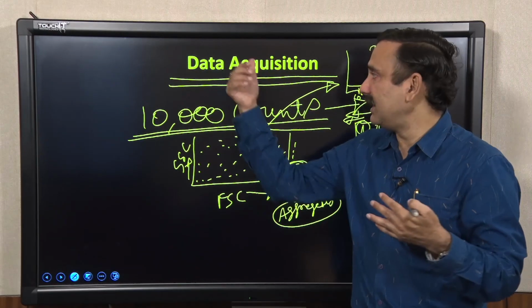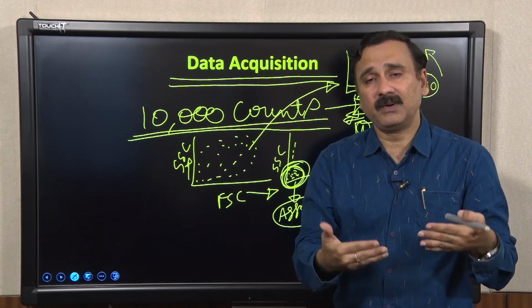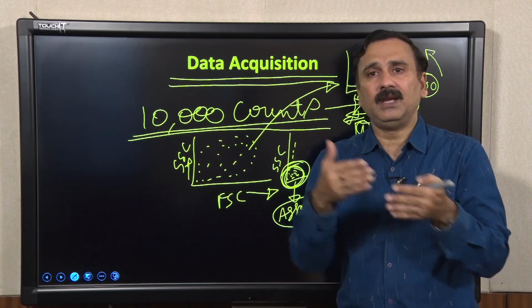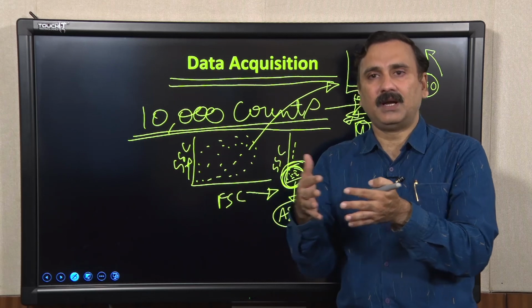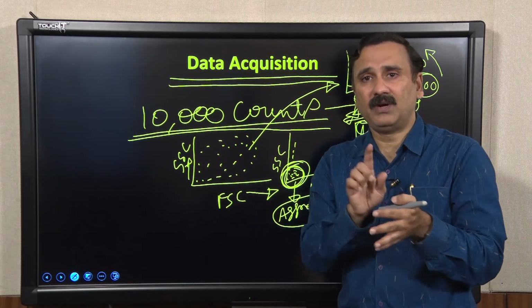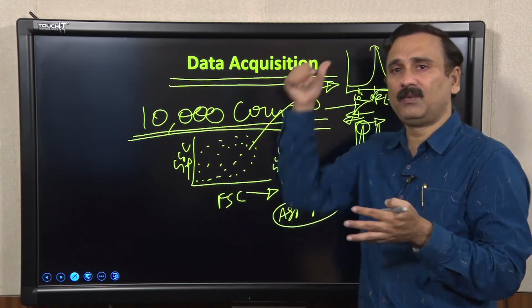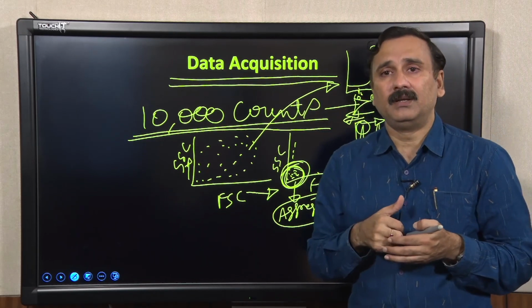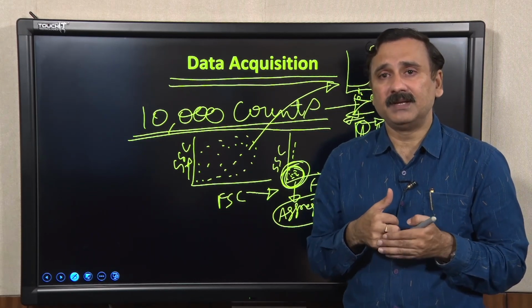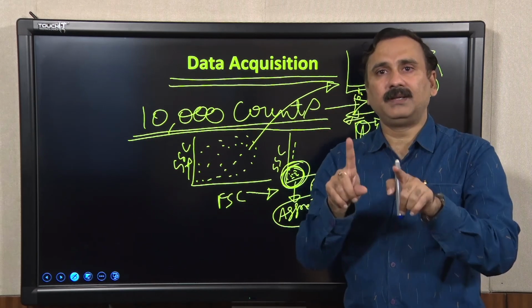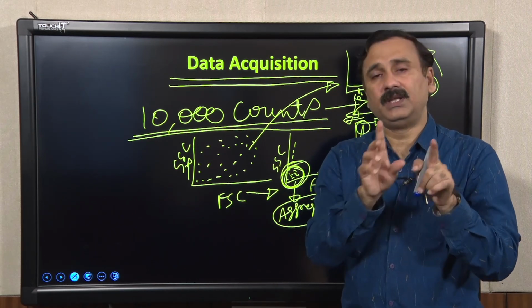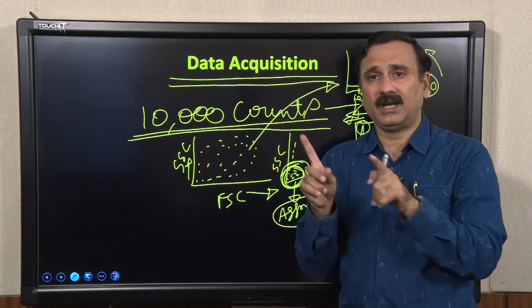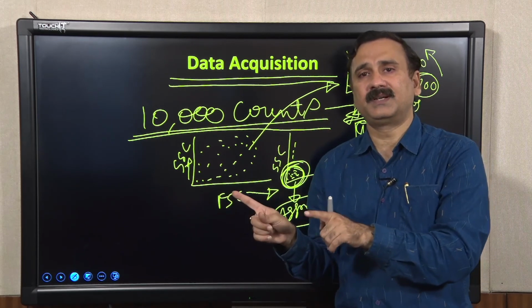That is why the data acquisition has to be done on multiple occasions. Once you see the control samples and the untreated sample, you have to modulate the untreated sample with the help of the current as well as the gain settings. Once you get the right positions, you should not change the current and the gain conditions, and then you analyze your treated samples.